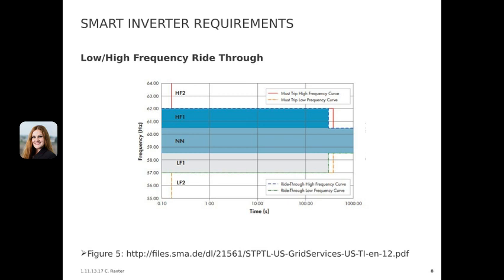Similarly to the low and high voltage ride-through, the utility dictates the values that are predetermined for the location where it's going to be installed to ensure that the minor fluctuations that they've determined to be normal operation will not cause a large amount of DERs to immediately trip offline, and that they will stay connected for a predetermined amount of time to ensure that you don't have nuisance tripping with a high percentage of DERs dropping offline.